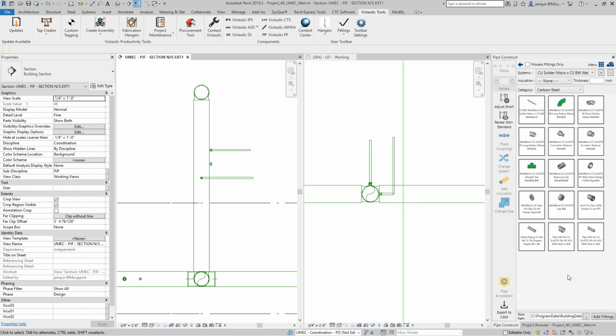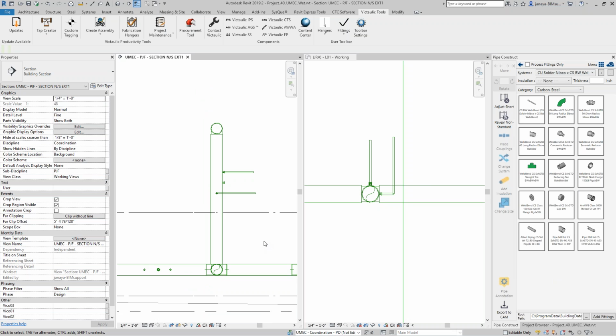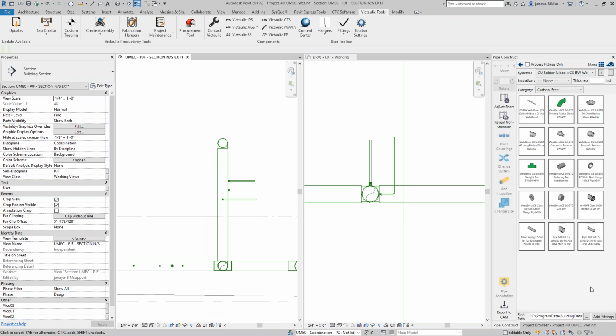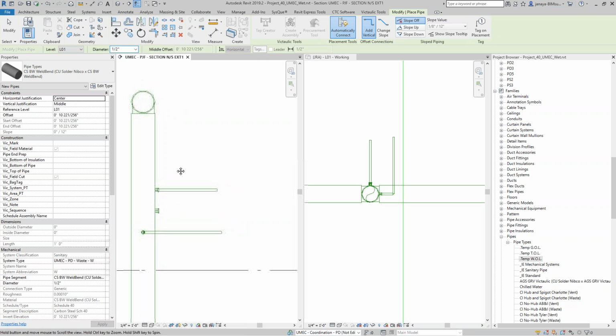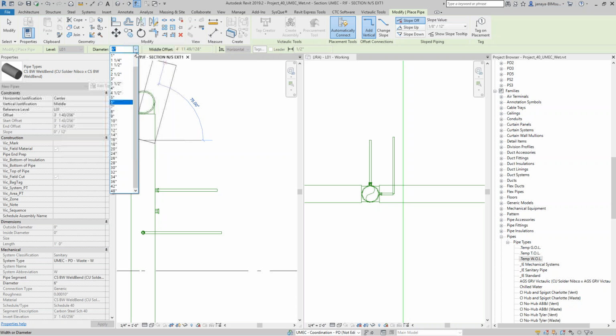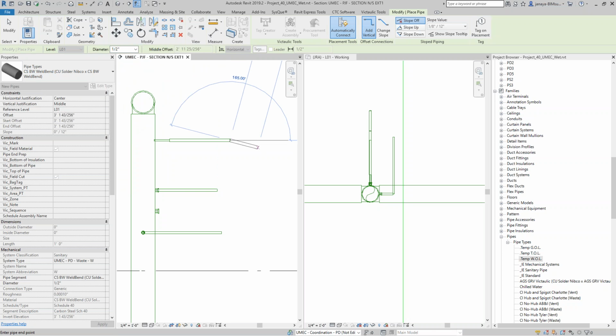Unfortunately, in this situation, Paul's really going to be the only person modeling. So I don't think we'll have any work sharing issues if we choose to go that route. See, if that's the case, any view you're in, you can take off with a tap. It's just Revit's not gonna have the button mapping like fabrication does. So it's not going to include all the pieces in between the tap and that copper line you want to put.